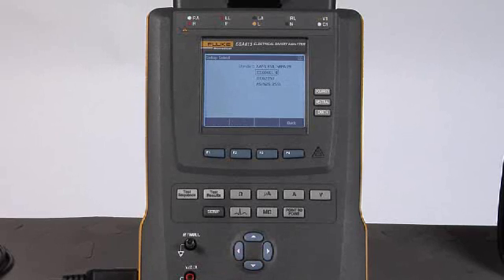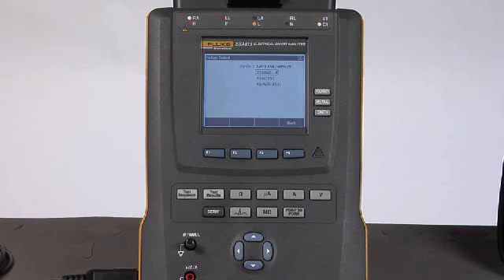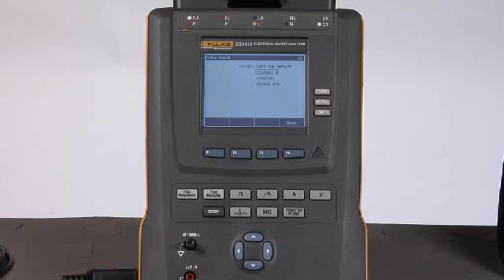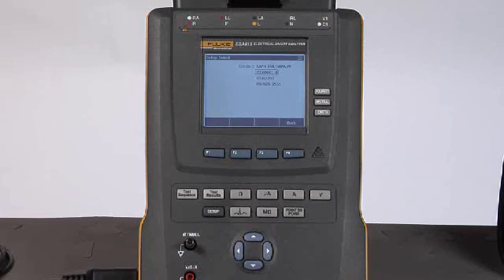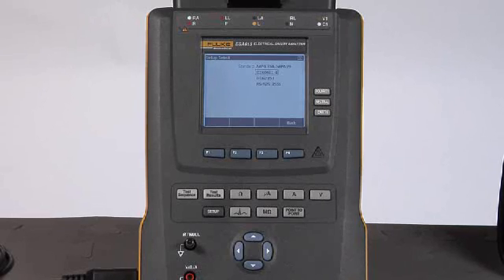And I can select from a list of US and international standards that will form the foundation of the tests that I'm going to do. The rest of the controls on the ESA615 should look very familiar to you, as they are the same as those buttons you will find on the ESA612 and ESA620.